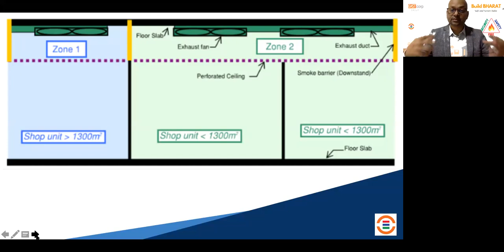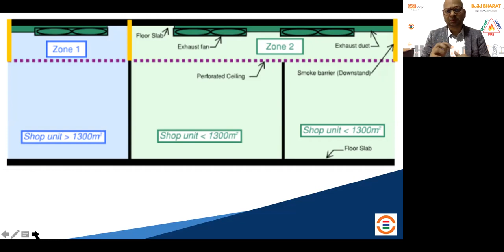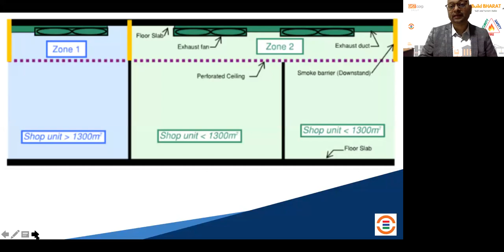So fire sealant, fire doors, your fire rating, the passive materials are going to play a vital role. On top of that, engineering controls like smoke management systems, smoke dampers, fire dampers, lift well pressurization, stairwell pressurization, smoke management controls - everything is part of the entire system, so that in case of any eventuality, it can take care of it.